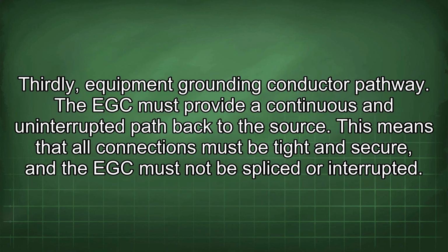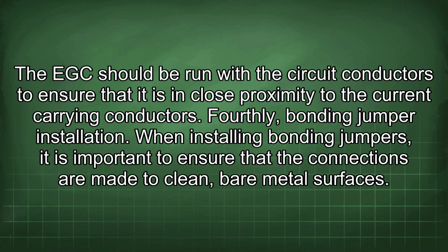Thirdly, equipment grounding conductor pathway. The EGC must provide a continuous and uninterrupted path back to the source. This means that all connections must be tight and secure, and the EGC must not be spliced or interrupted. The EGC should be run with the circuit conductors to ensure that it is in close proximity to the current carrying conductors.